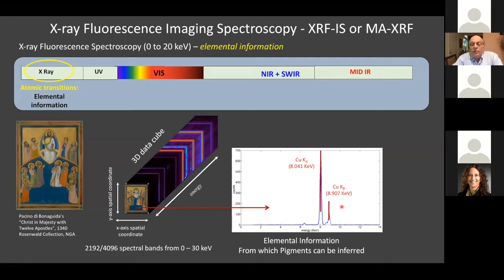Now, right off the bat, you can see from a signal processing point of view, there's a certain advantage to XRF. Instead of those broad reflectance spectra I showed you, now we have narrow emission peaks. And more importantly, scientists know exactly where a given element will give its emission. So we can be more deterministic in terms of the identification.